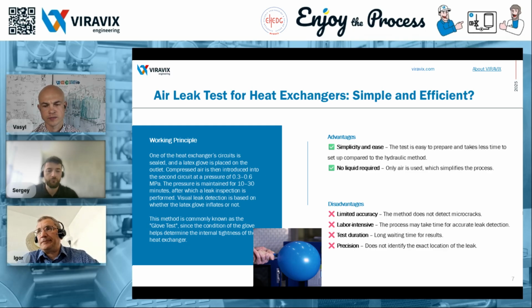In fact, this is standard practice in all the companies I've worked with. But it can't be considered a control measure that guarantees the product won't be contaminated. Rather, it's part of good manufacturing practices. One of the prerequisite programs needed to maintain a hygienic production environment. And that's why leak tightness testing of heat exchangers and their regular maintenance should go hand in hand with pressure difference control. It should also be noted that if there's always excess pressure on the product side, then in the event of a leak, we'd constantly be contaminating the heat transfer medium, thereby increasing the risk of cross-contamination elsewhere in the production process.